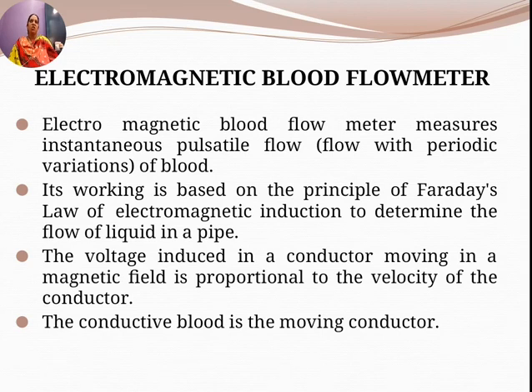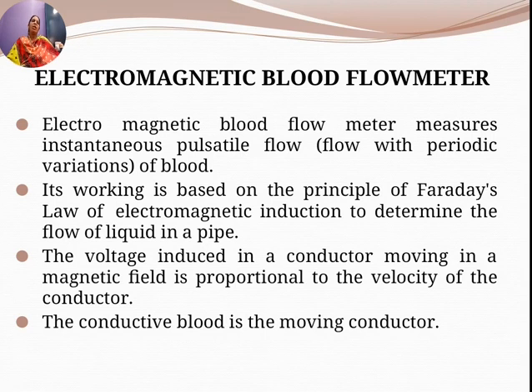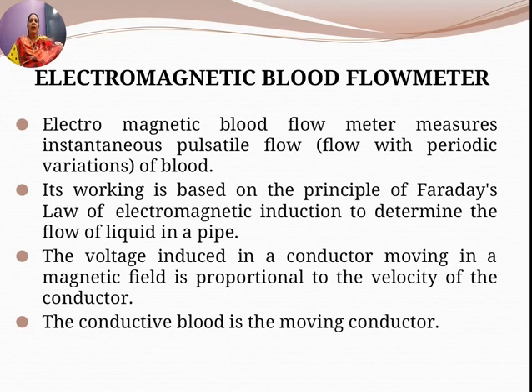It works on the principle of Faraday's laws of electromagnetic induction to determine the flow of liquid in the pipe or blood vessel. This law states that the voltage induced across a conductor as it moves at right angles through a magnetic field is proportional to the velocity of that conductor. In this case, the conductive blood is the moving conductor.